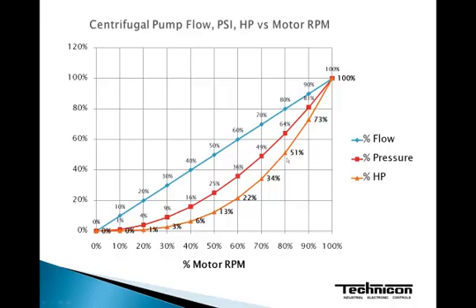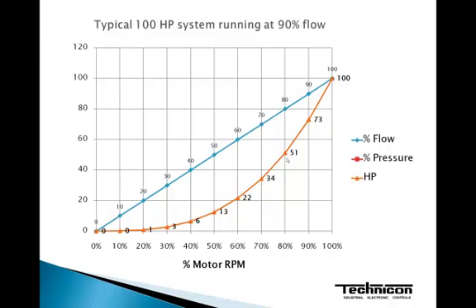Or if we back this down to 80%, we would have 51% of the horsepower required. Looking at actual horsepower, let's say we had a 100 horsepower motor and pump system running at full flow or full RPM — 100% — then we would require 100 horsepower. But if we back that flow down to 90%, then we would require only 73 horsepower. And if we take it down another 10% to 80% flow or RPM, we reduce this by a whopping 49%, so we only require 51 horsepower at that point.